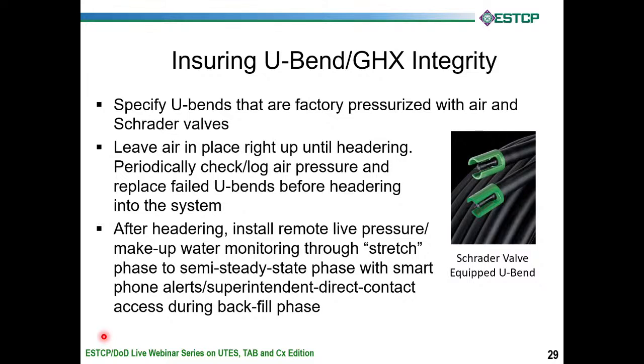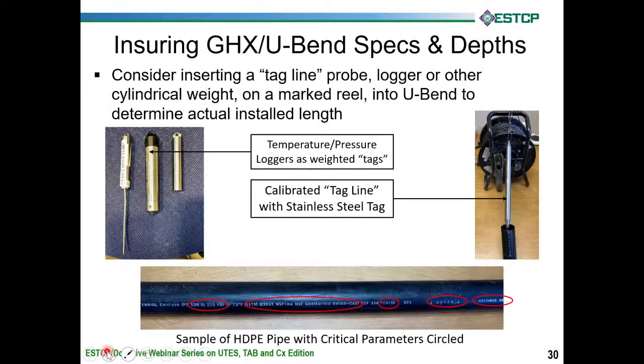Because like Brandon said, when you saw that big plummet in pressure, we actually called the contractor. Brandon and I and Joey, we all had this on our iPhones, so we got an alert, called them immediately. They went out, found the leak, found the nice wet spot in the Georgia clay there, and knew exactly where it was. And so it took them a few days to get it fixed, but in the end, it turned out to be a very beneficial thing. So we like live pressure monitoring during all backfill procedures.